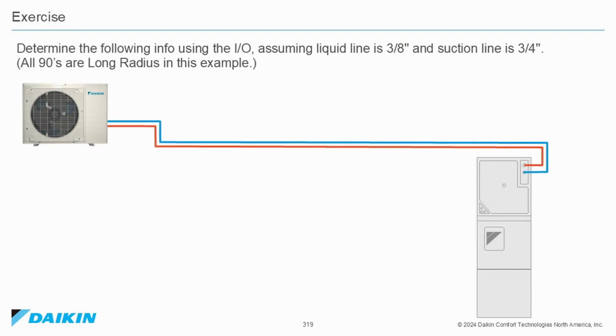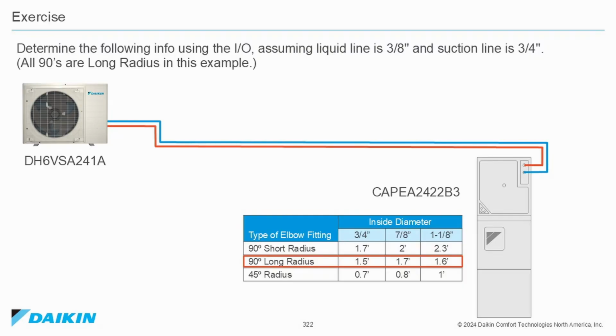Let's do an exercise. We will determine the following information using the I/O manual, assuming the liquid line is 3/8 inches and the suction line is 3/4 inches. In this example, all 90-degree elbows are long radius. For this exercise, we will use the DH6VSA241A outdoor unit and the CAPEA2422B3 indoor air handler. This chart shows the inside diameter of the long radius 90-degree elbows.